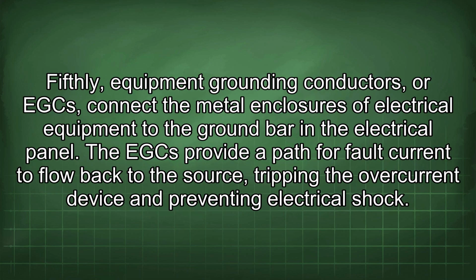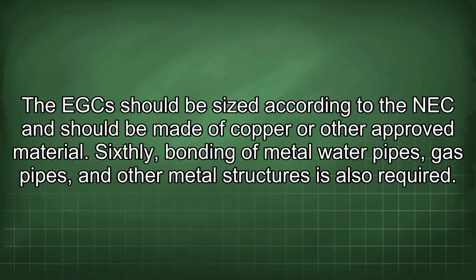Fifthly, equipment grounding conductors, or EGCs, connect the metal enclosures of electrical equipment to the ground bar in the electrical panel. The EGC provides a path for fault current to flow back to the source, tripping the overcurrent device and preventing electrical shock. The EGC should be sized according to the NEC and should be made of copper or other approved material.